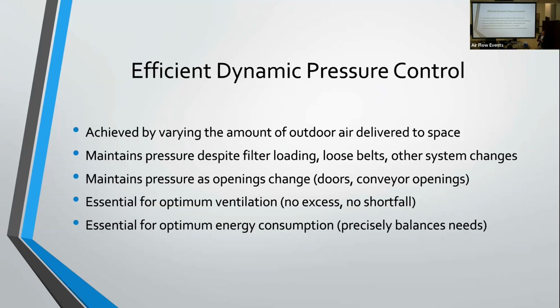When your system changes in the building, say your dock doors open up, your exhaust fans kick on and off, your system's changing, so the makeup air unit needs to react to that change in system type. So that's what this dynamic pressure control does. So it accounts for that. It also accounts for things at the unit itself, like say filters load up or belts loosen up. It also automatically will account for those things. So no matter what's happening in space or at the unit, the system automatically adjusts to maintain that optimum efficiency to achieve those positive pressure results.